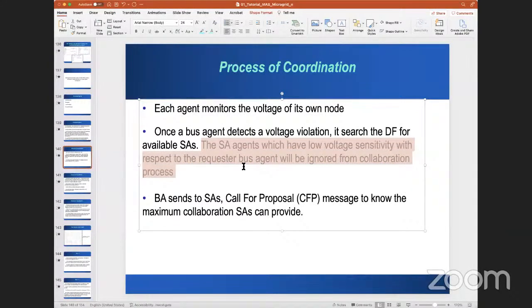That's exactly what I was mentioning - you need to study your system and then decide on the sensitivity thresholds. For example, if a change of more than 5% occurs, I want to incorporate that as within reach of that agent. So if capacitor control changes at bus 1, 2, 3, or 4 cause up to 5% change, then all those buses are within the region of influence of that particular agent. Anything below 5%, I will say my agent is not influencing.